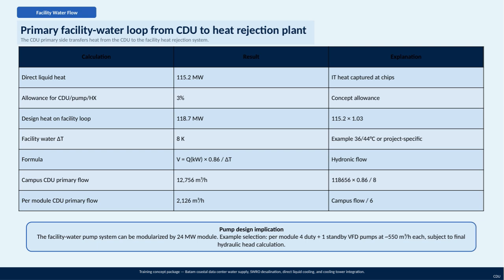Using the hydronic flow formula, the campus-level CDU primary flow calculates to approximately 12,756 cubic meters per hour, which when divided by 6 modules results in per module flow of about 2,126 cubic meters per hour. On the pump design side, the facility water pump system can be modularized around a 24 megawatt capacity per module. For example, each module might be served by 4 duty pumps plus 1 standby variable frequency drive pump, each with a flow capacity of around 550 cubic meters per hour. Final pump selection will depend on detailed hydraulic head calculations, ensuring the system is optimized for efficiency and reliability.